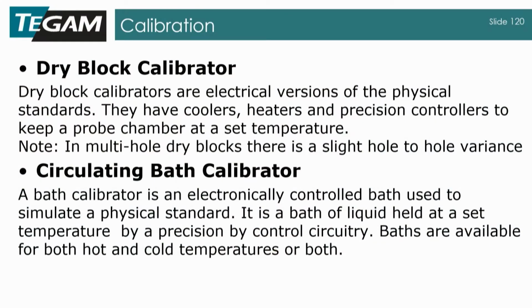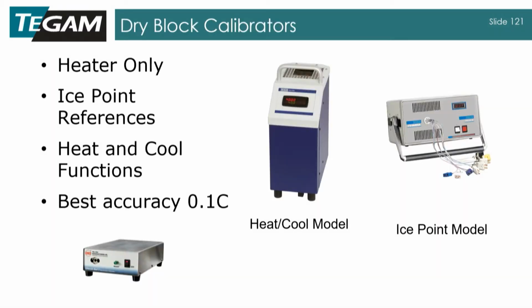All right. So calibration. Let's talk a little bit more in depth about calibration. You've got dry block calibrators. We talked about circulating bath calibrators. Here's what some of these look like. Here's a basic calibrator. You've got a cavity here, and you put your probe in. There are some heat and cool models, so you can do different temperatures. This is always a pain, of course, because whenever you change the temperature, you have to wait a long time.